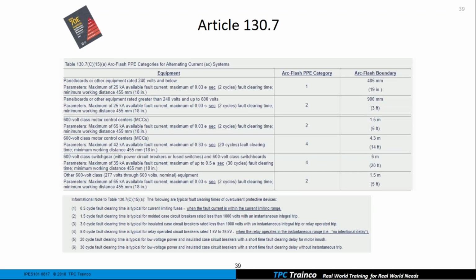Now we are looking at method number 2 to generate our labels and our personal protective equipment, what we might have to wear. So this is the PPE category method. Table 130.7C15 has been in these editions of 70E for the past 3 cycles. So if we look at it, we can see some equipment to the left. And if we look at the very first one, panel boards or other equipment rated 240 volts and below.